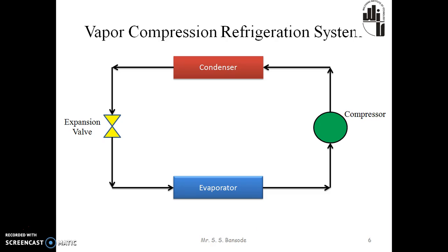Let's have a look at how the vapor compression refrigeration system works. When the compressor is started, it draws the low-pressure vapor from the evaporator — it may be wet vapor, dry saturated refrigerant, or superheated vapor — and compresses it isentropically to a sufficiently high pressure. Since the compression work is done on the vapor, its temperature also increases. The hot vapor from the compressor under pressure is discharged into the condenser, where it is cooled at constant pressure by rejecting heat to the condenser cooling medium, usually water or surrounding air. This converts the hot vapor into saturated liquid.